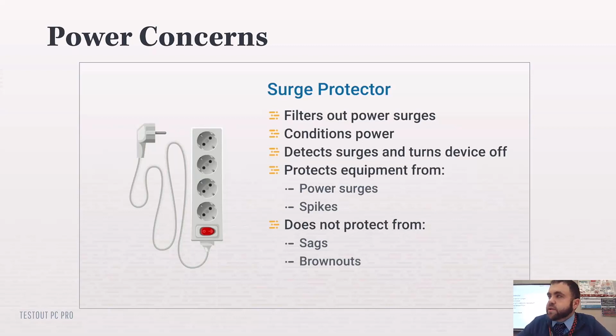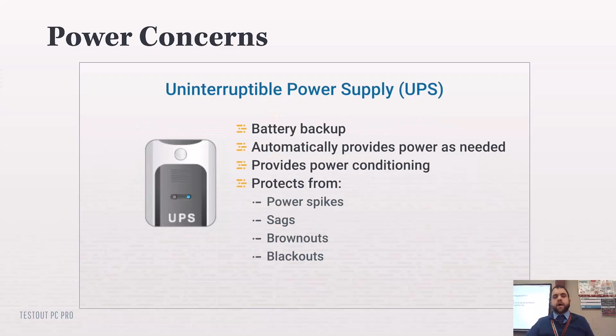So surge protectors, do they have batteries? No, if they did, they would be UPSs. Surge protectors just help protect us from those spikes. They have some technology built in to normalize and condition the power, it's a power conditioner. It detects that surge and clicks the button so it'll save your device. Notice what it does not protect from: sags and brownouts. A sag is when it goes too low, a spike is too high. And also a brownout, where it's just constantly not getting enough voltage. That's where the UPS comes in, where it'll actually condition our line for us.